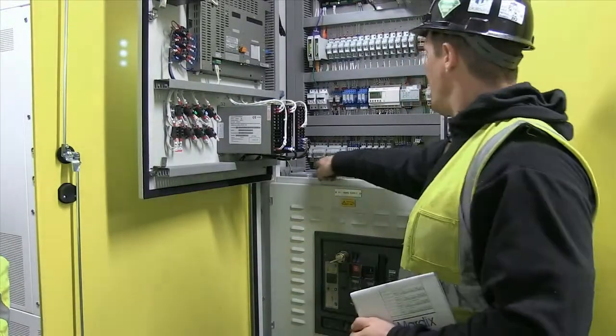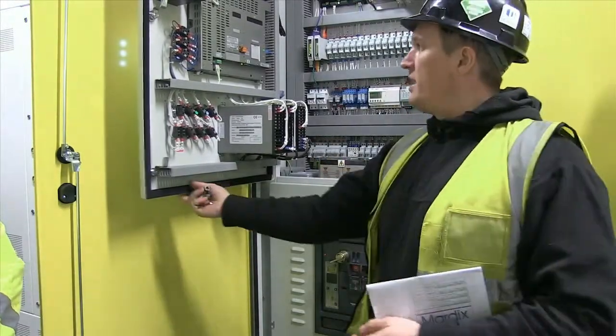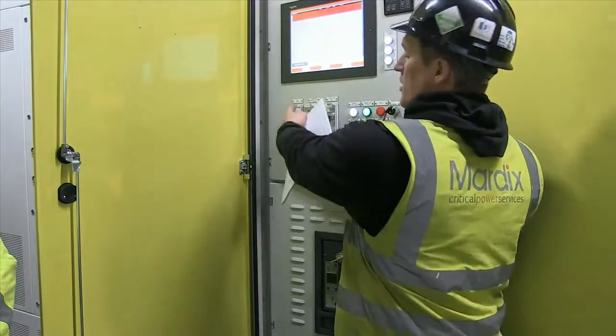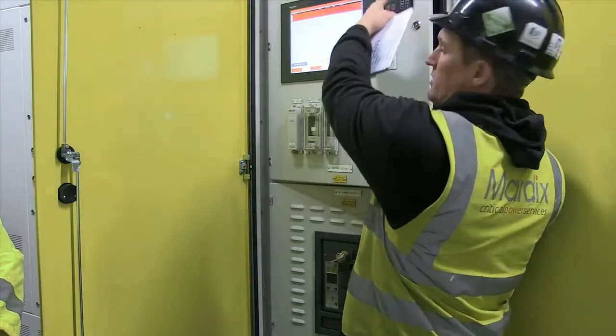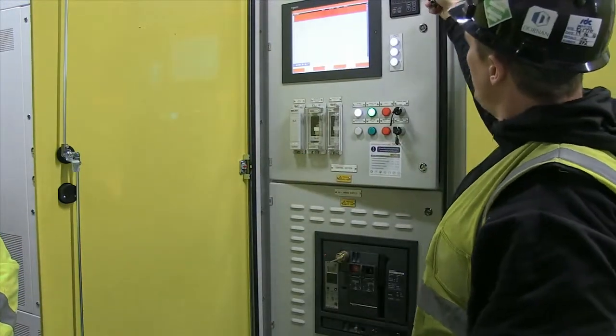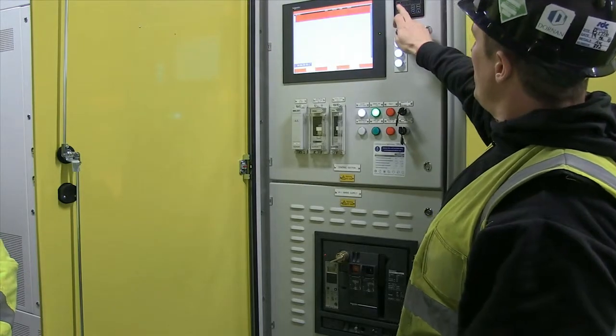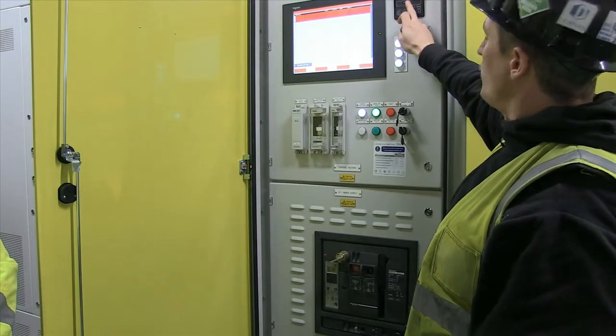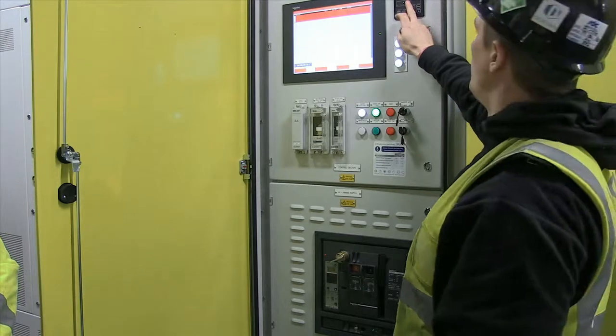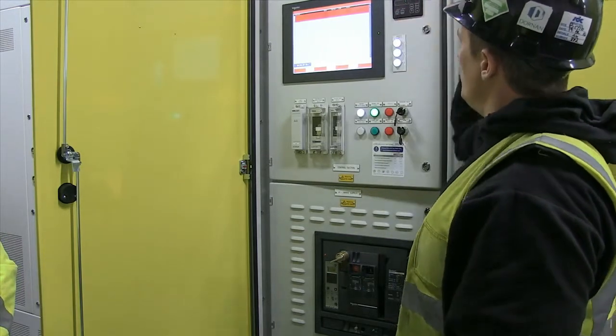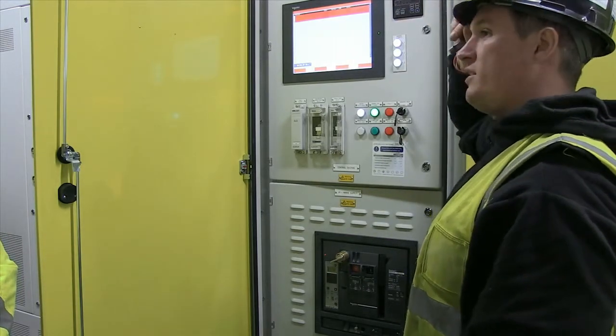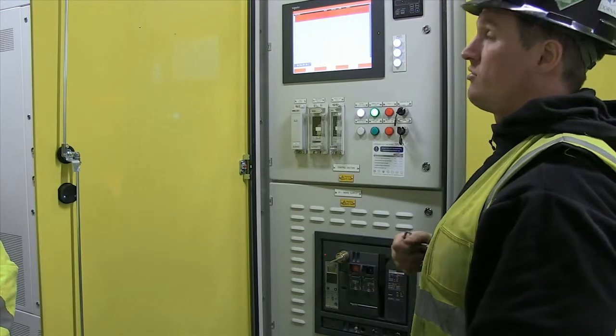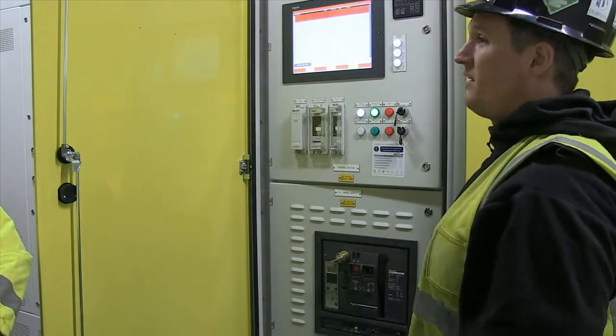Whilst we're in here, battery backup. The battery backs up all of your protection. So it backs up this system here and this system here. And the temperature relay here, pretty obvious, core 1, core 2, core 3, core 4 is turned off because we don't have a fourth core. Mm-hmm. And there are the settings. Your settings are, I believe, 90 degrees for an alarm and 119 degrees for a trip. Shouldn't really, in theory, go anywhere near them.